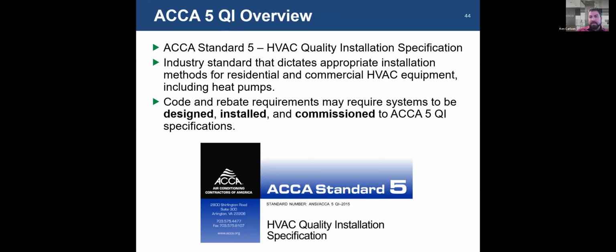So again, just a little synopsis on ACCA 5 quality installation. It's basically a guideline. It's a specification for the installation of HVAC equipment. It's an industry standard that dictates appropriate installation methods for residential and commercial HVAC equipment, inclusive of heat pumps. And again, reiterating from before, I know I showed the slide already, you could be required to document and adhere to ACCA 5 for either local codes or even to obtain certain rebates.